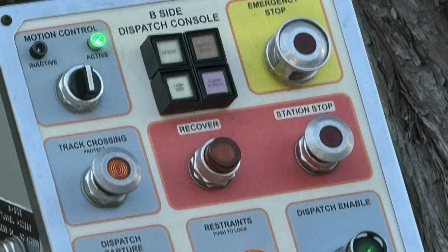The next one is a common question I get on email a lot. Hey, what's the difference between ride stop and e-stop? Well, that's really just a difference in recovery. That's what you have to look at that as. So a ride stop is simply pushing a stop button, and it typically stops motion. It tells the rides to stop. When they come up into the brakes, it says, hey, stop the ride there, and it brings everything to a halt. An e-stop will also do the same thing, except a lot of times it won't let you recover the ride without going through a full startup process.